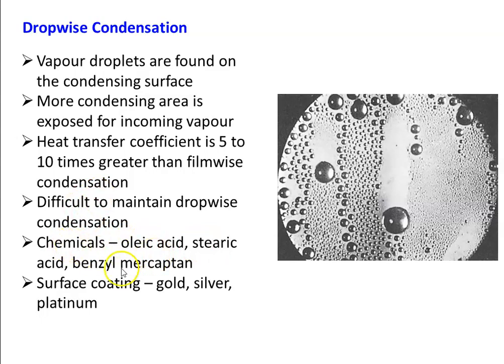Drop-based condensation can be maintained by applying chemicals on the surface such as oleic acid, or by surface coating with gold, silver, or platinum. However, surface coating with precious metals is very costly. Applying chemicals works only for the initial few hours — after continuous flow of vapor and liquid, the chemicals are washed away and film-based condensation resumes. So condensers are normally designed only for film-based condensation.